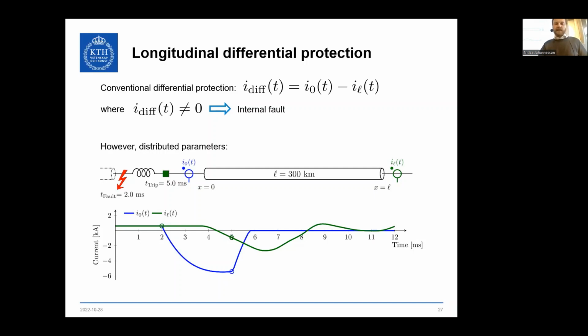There have also been some proposals on introducing a blocking scheme, because you can look at the polarity of the difference between the currents. An external fault in the backward direction in this case will have the opposite sign. The problem is that you increase the security of the protection, but you reduce the dependability, because you can actually block the protection during an internal fault.